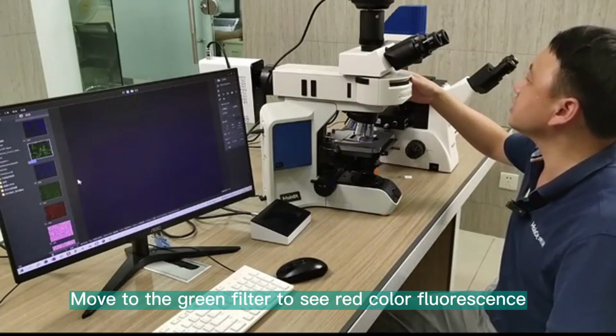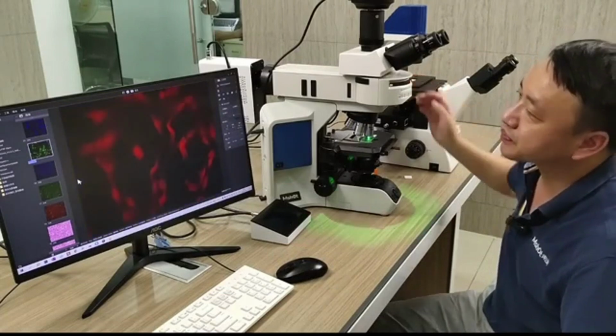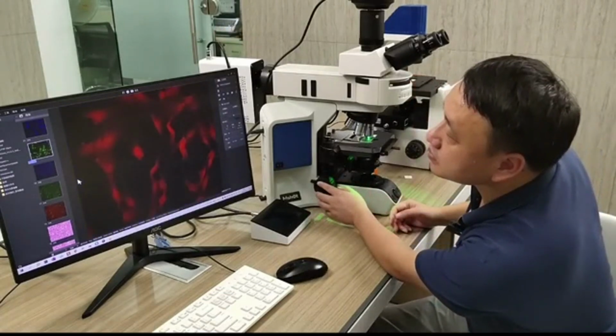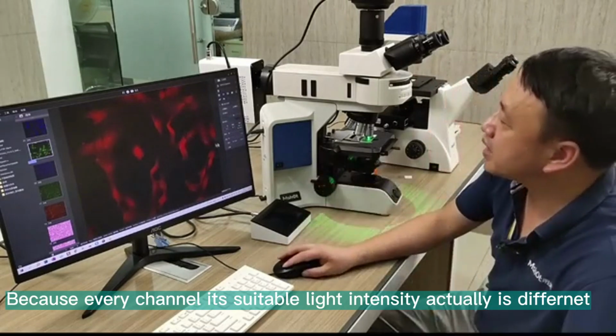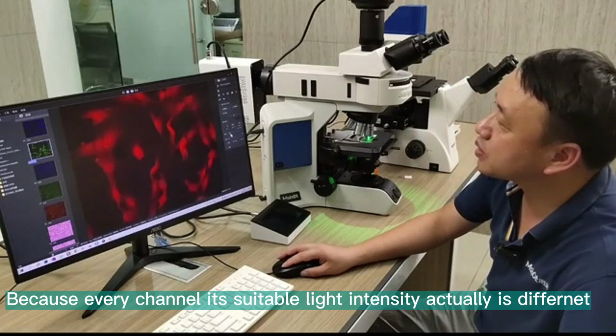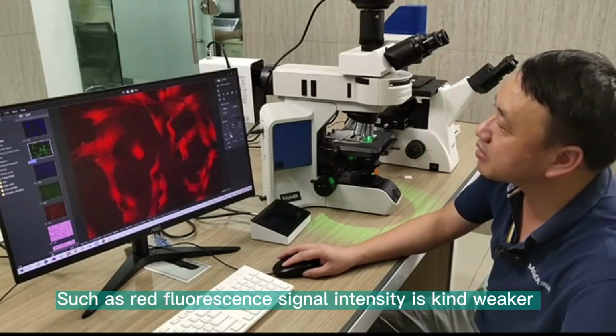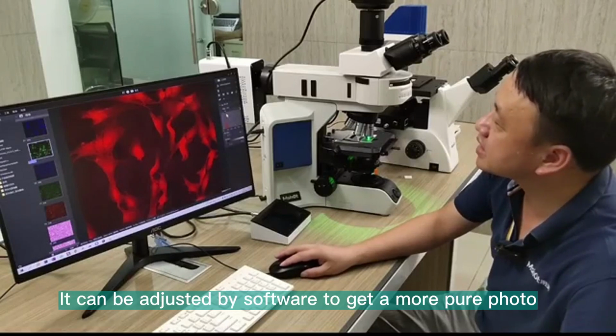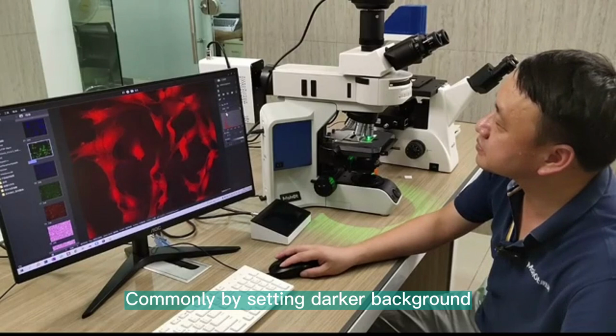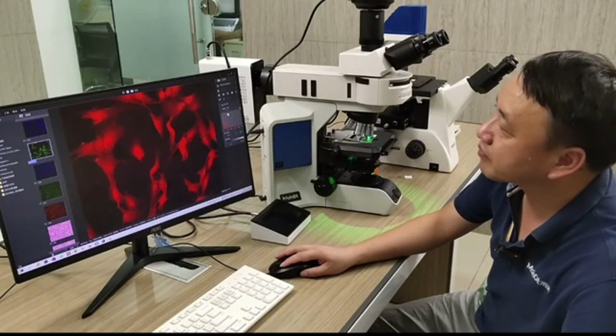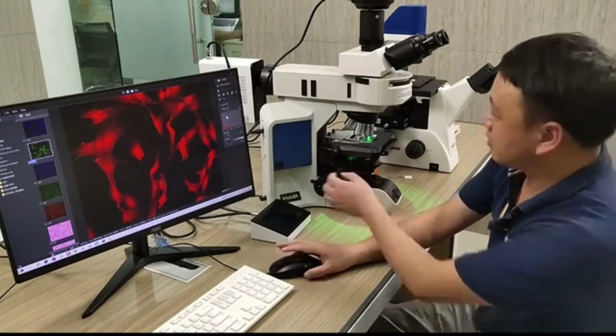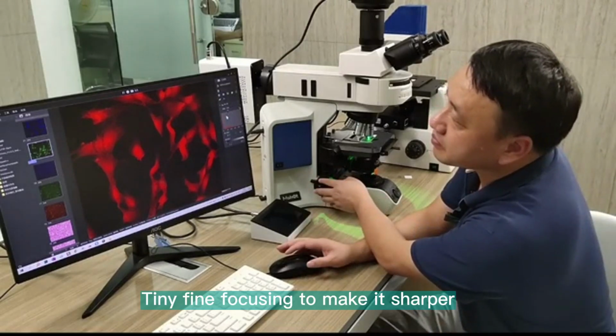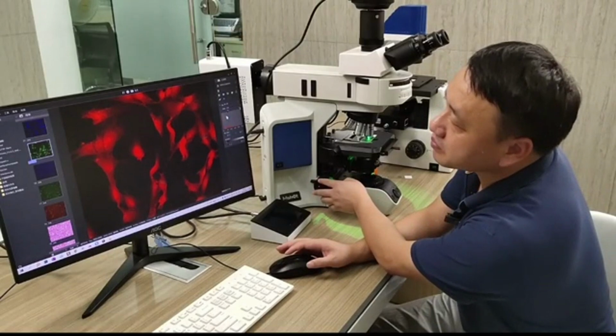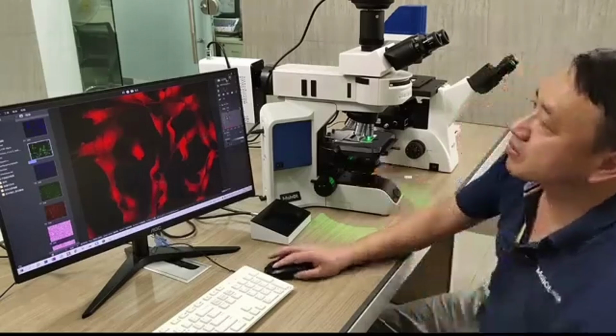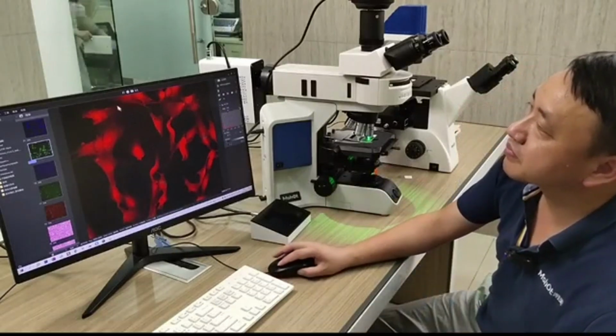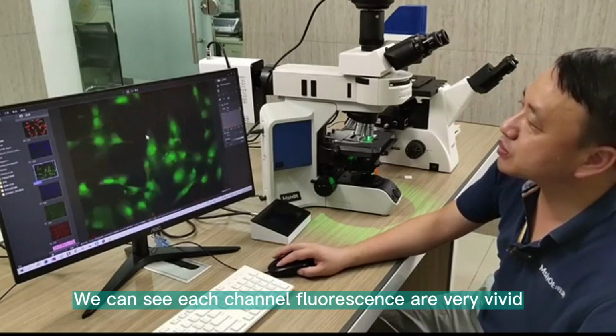Move to the green filter to see red fluorescence. Because every channel's suitable light intensity is actually different. For example, the red fluorescence signal intensity is weaker. It can be adjusted by the software to get a purer photo, commonly by setting a darker background. Tiny fine focusing to make it sharper. Let us take a photo. We can see each channel's fluorescence is very vivid.